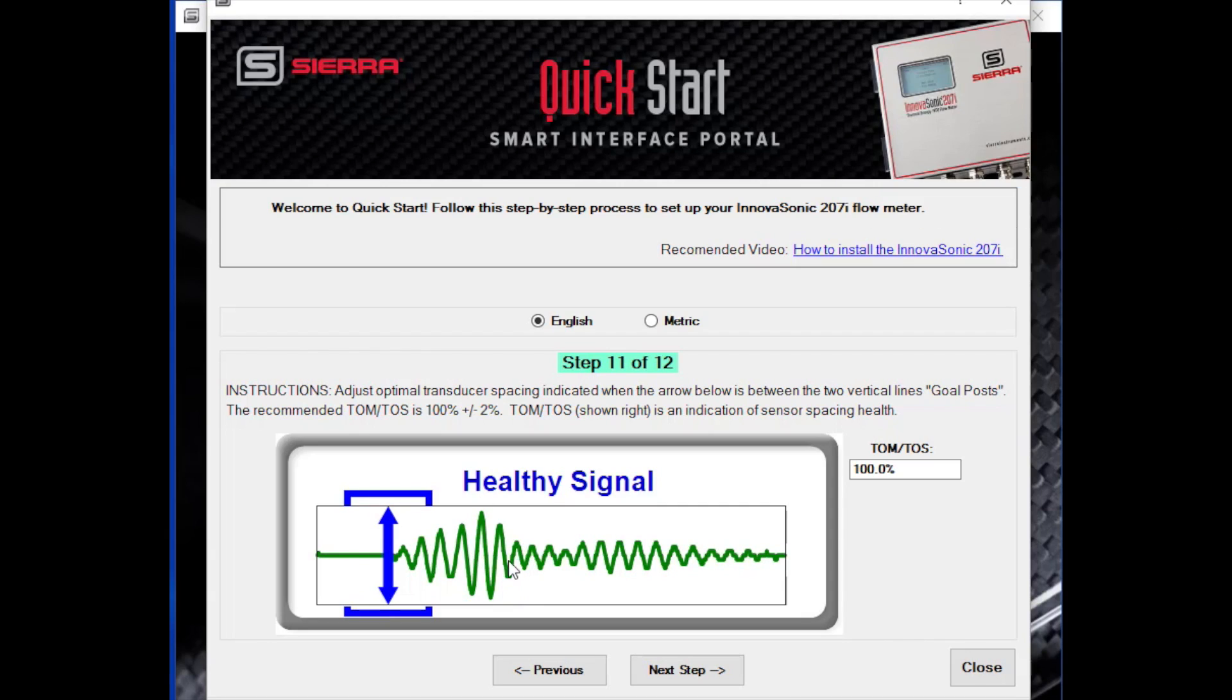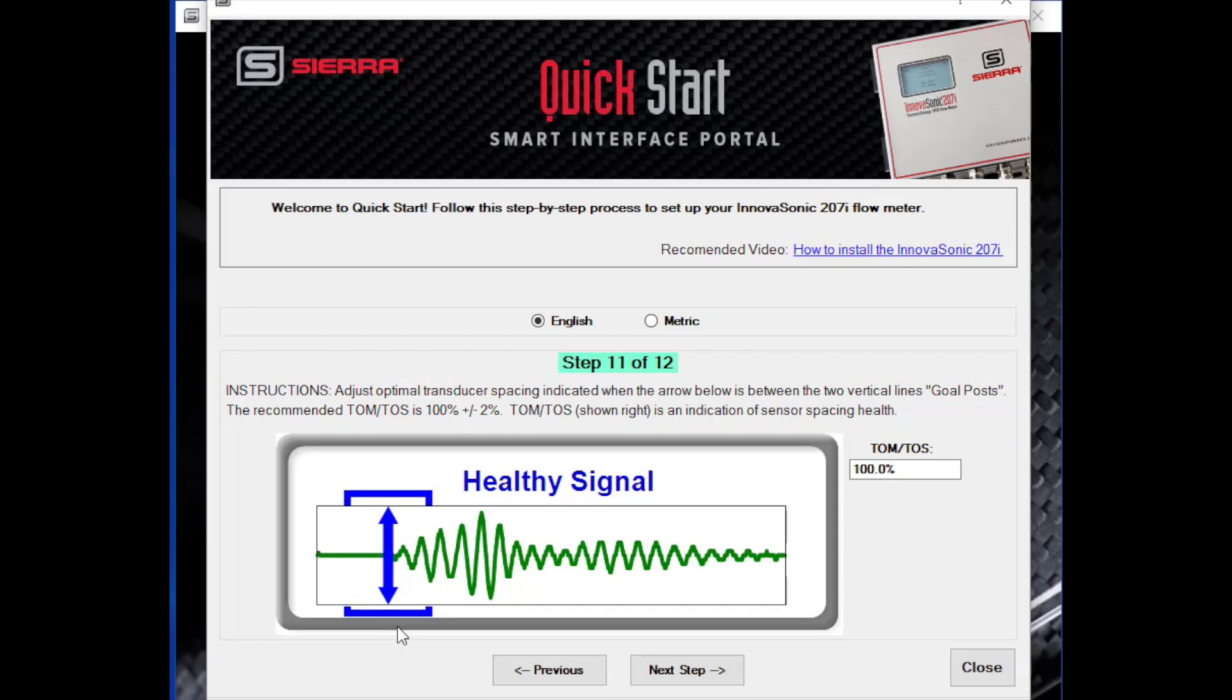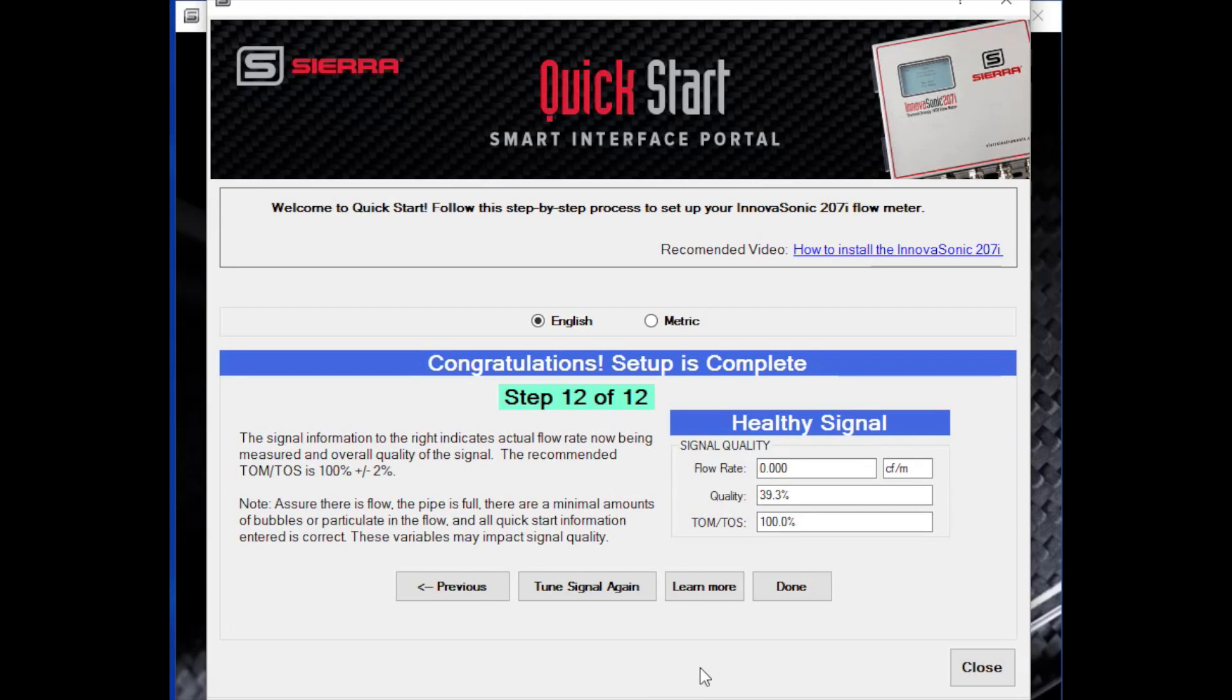Here you see the sensor waveform. So this is the actual pulse that is being transmitted from the upstream transducer to the downstream transducer and then the other way. What we want to do to get a healthy signal is to take the beginning of this pulse, put this arrival marker, as we call it, this up and down arrow here, between these two goal posts. So these are the goal posts. This is the arrival marker that marks the beginning of the pulse. And for optimal performance, that needs to be in between these two goal post markers. So if you need to make some adjustments, leave one sensor fixed, move the other sensor towards or away until you get the arrival marker in between the goal posts. Once you have all that, you have a good signal and verify that with the final step. It will look at your signal quality, your TOM over TOS, and you're ready to start taking measurements.